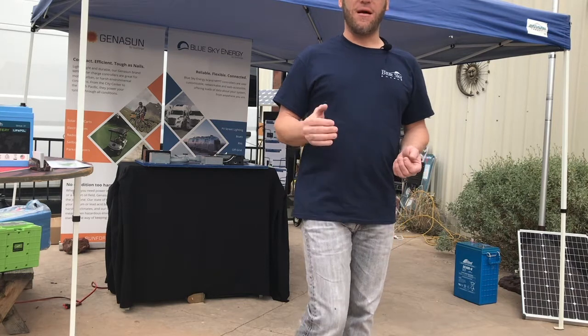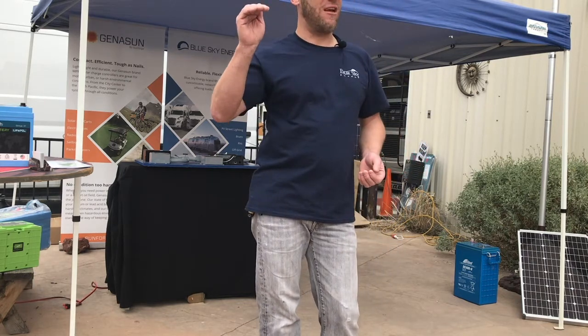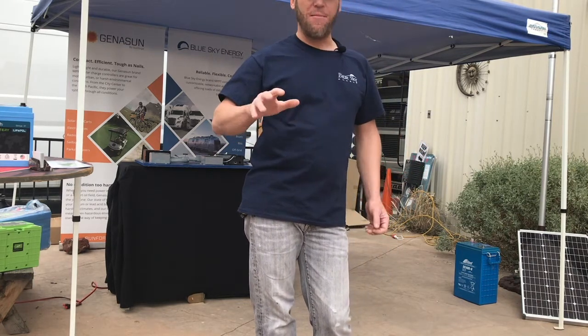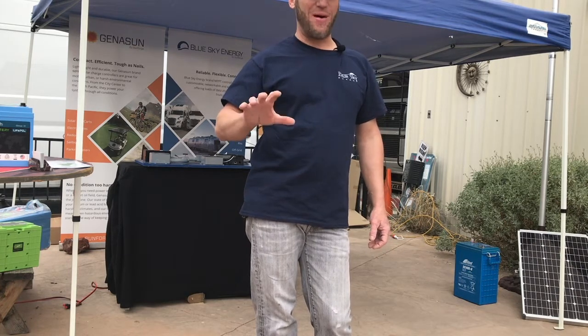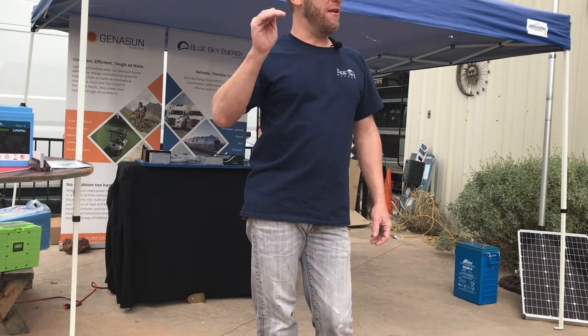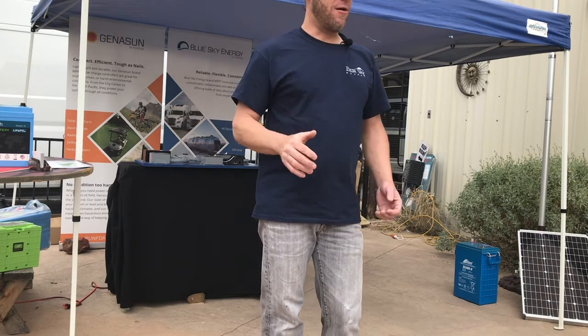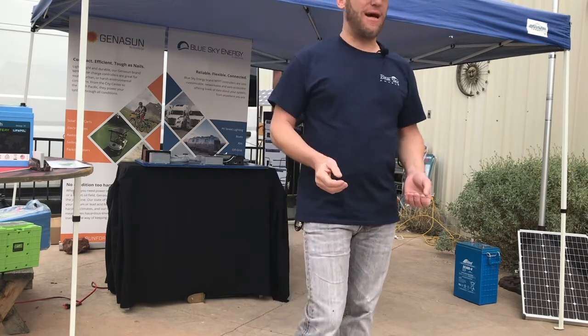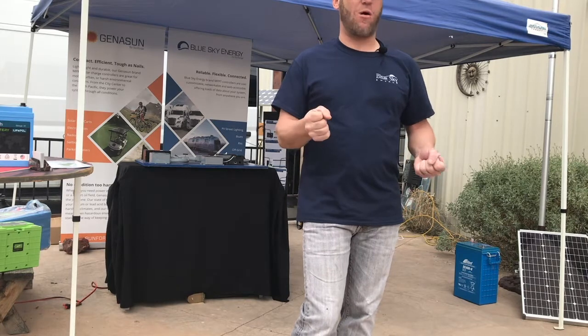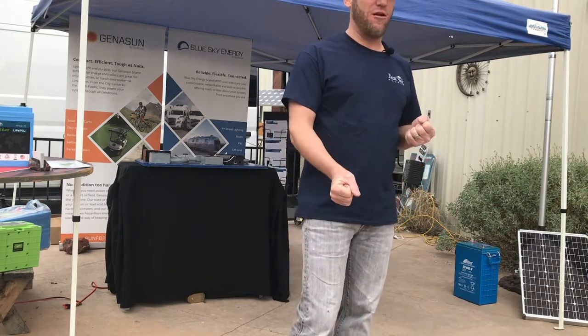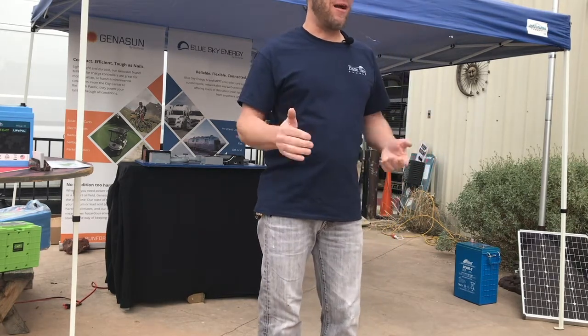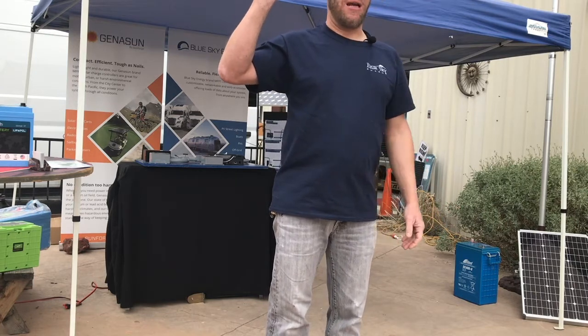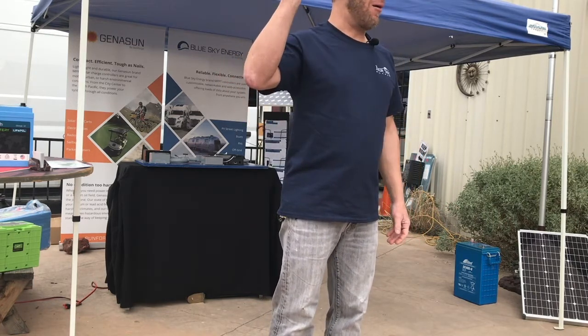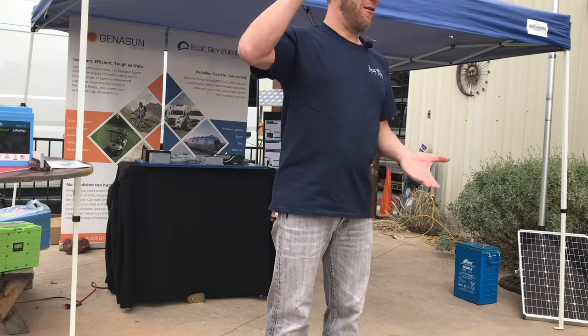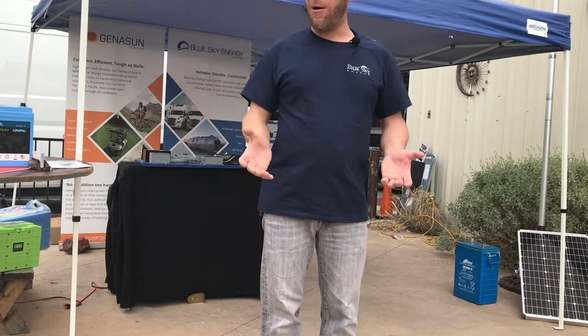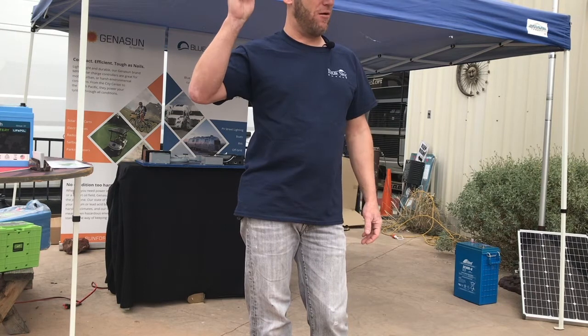The other way to maintain that voltage or base that transition to the lower float voltage, which will be about 13-ish depending on what type of battery you have, is to base that on the net current reaching the battery. Now, your resting voltage of your lead acid battery is probably going to be about 12.5, 12.7 if it's pretty new. So if you're maintaining that battery at 14.4, let's say, that's always going to take some power to make that happen - you're not down here, you're up here. So it's always going to take some amount of power to keep that battery at that higher voltage.